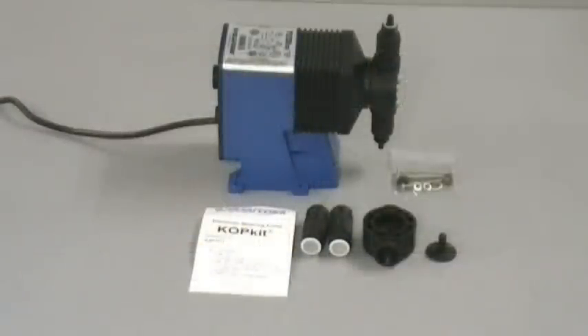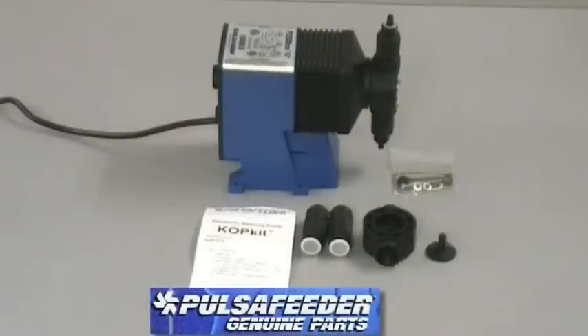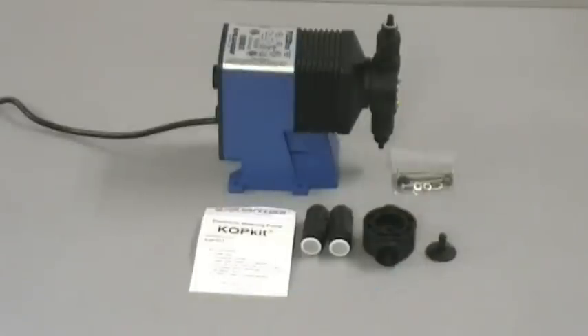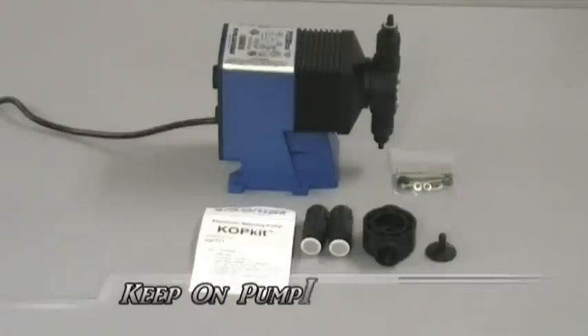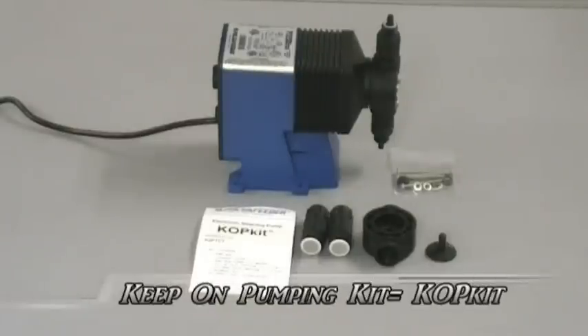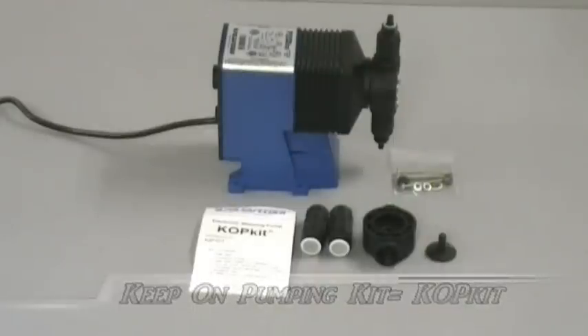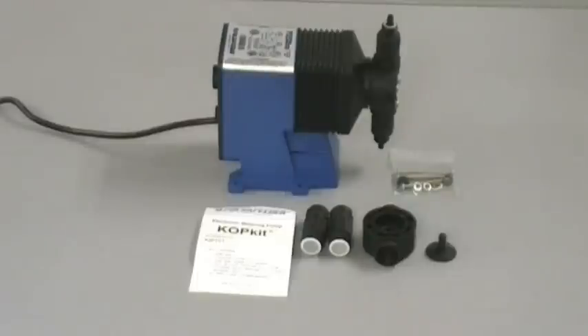In order to ensure optimum performance, the Pulsatron series metering pumps require periodic inspection, cleaning, or replacement of the liquid end parts. It is generally recommended that the pump is inspected every 6 months. Depending on the application, the maintenance frequency for the pump will vary. Pulsatron keep-on pumping kits, or KOP kits for short, include the most common items for preventative maintenance. However, other system components such as suction and discharge tubing and all fittings should be checked for potential problems.